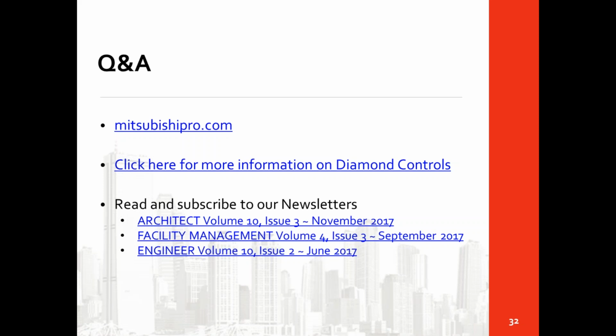Sure. For the most part, VRF manufacturers are offering what are called BACnet gateways—a device that connects to the VRF system and provides visibility on typically one of the standard protocols, so existing building controls can operate the VRF. Mitsubishi Electric can offer that as an option too, but one of our differentiators is that we have a seamless branded solution, directly operating both the VRF equipment with controls and any of the other ancillary systems or equipment in the building. That's one of the ways we're definitely different from most of the market.